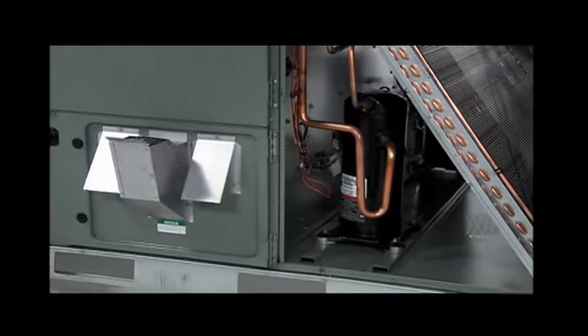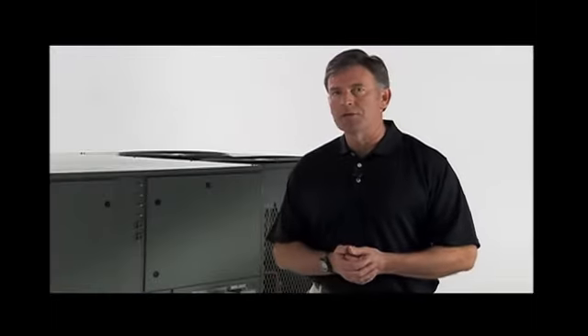81% steady state efficiency is maintained on both first and second stage by staging the multiple inducers to optimize the combustion airflow. The direct spark igniter assures reliable ignition in the most adverse conditions. This is coupled with remote flame sense to assure that the flame is carried across the entire length of the burner assembly. Gas supply can be routed from the side or up through the base.